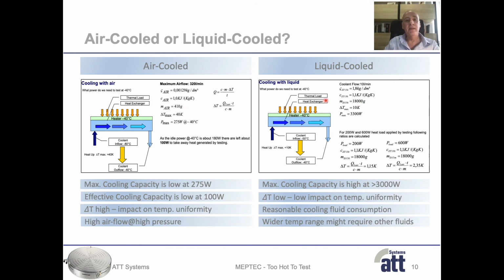The specific heat is similar. The delta T is 10 Kelvin, and therefore the calculated maximum power is over 3,000 watt, which is an order of magnitude higher compared to the air-cooled system. Another positive aspect of the liquid-cooled system is that due to the higher cooling capacity or cooling power, the delta T between the chuck temperature and the coolant inflow temperature is only 10 Kelvin compared to 40 Kelvin on an air-cooled system. Lower delta T's greatly help to get better temperature uniformities.